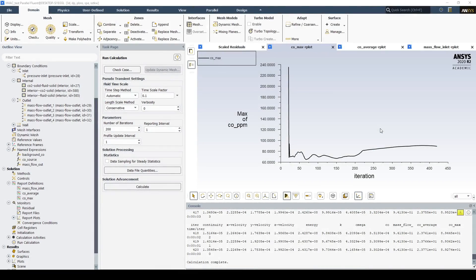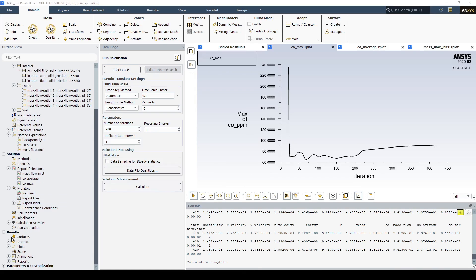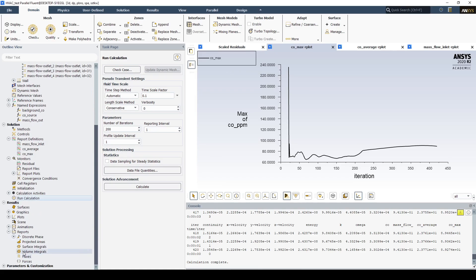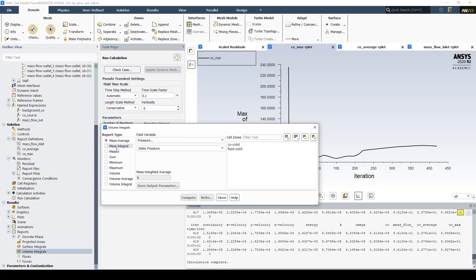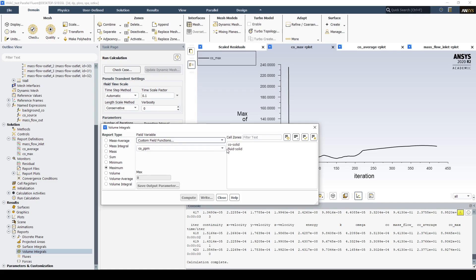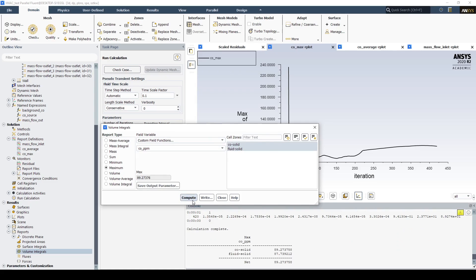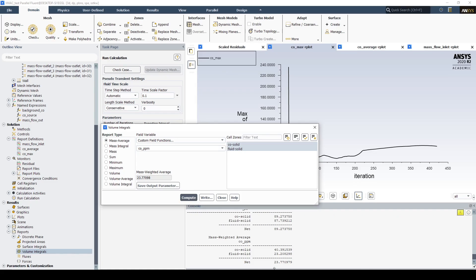To investigate the maximum PPM and the average PPM, we can use the volume integral reports. Going to volume integrals, choosing the maximum with the custom field function for maximum PPM, and computing it — we can see that the maximum is 89.3 PPM. Doing the same thing for the average, the average PPM is approximately 23.8.